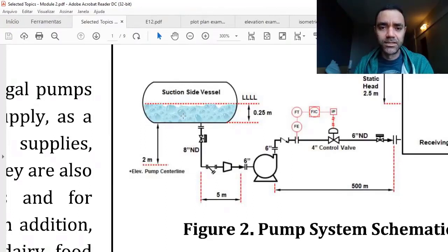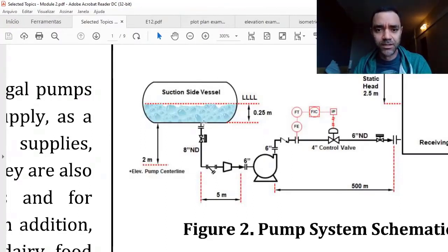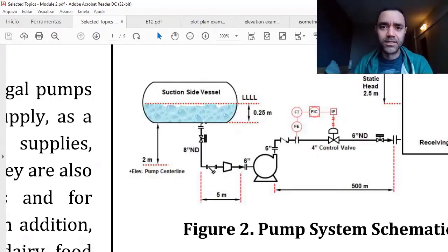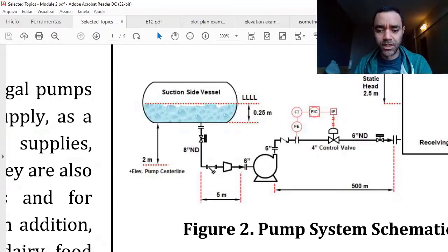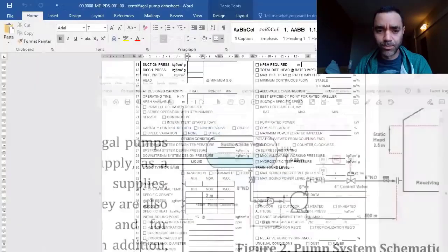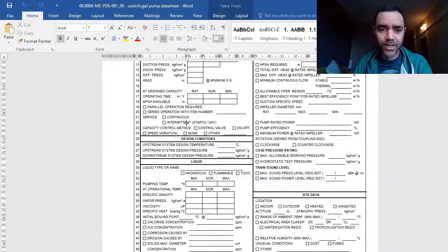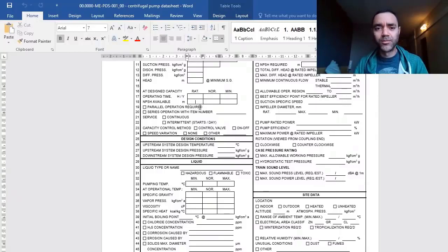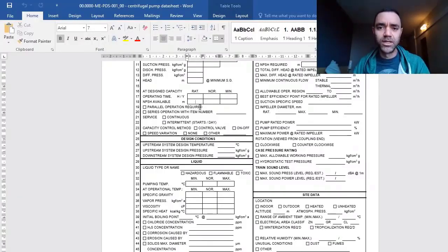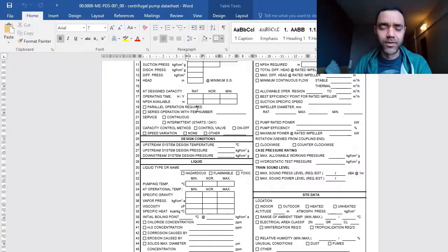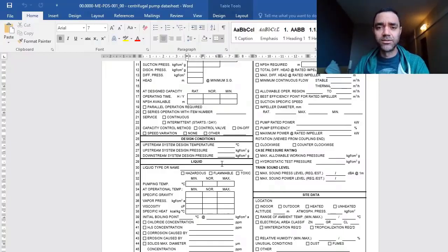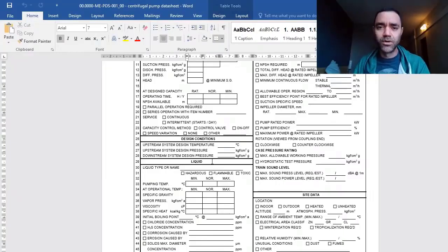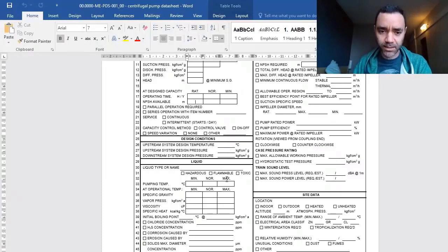Is it possible for this vessel to reach 10 bar G? It's not the operating pressure, but it is for design conditions, so you need to inform the supplier because eventually the seal of the pump will not be able to handle this much pressure and we need to add a pressure safety valve at the suction of the pump. All of this is part of plan design.